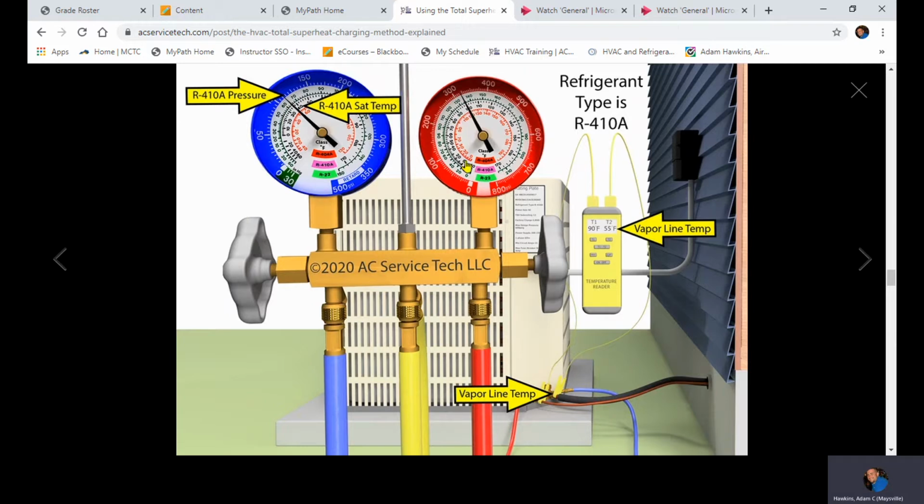There's your low side temps. We don't know what it is in the house in this picture, but let's assume that it's 70, 72. So we're running a 38-degree coil. That's not horrible, right? Indoor minus 30 to 35. So that's not bad.